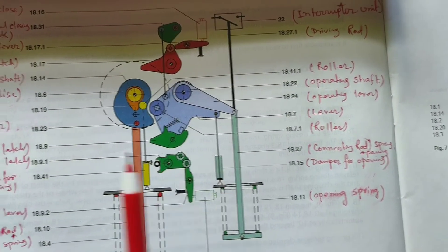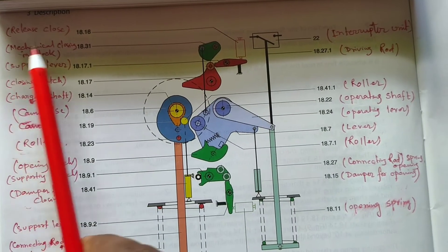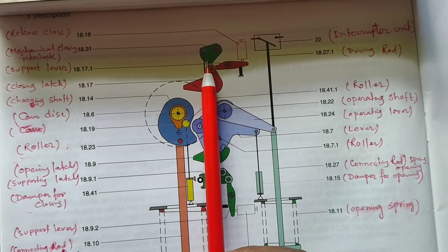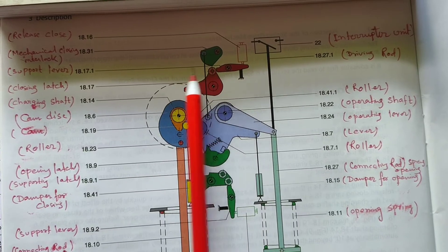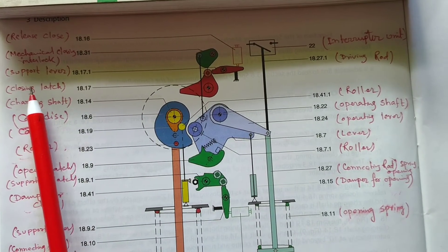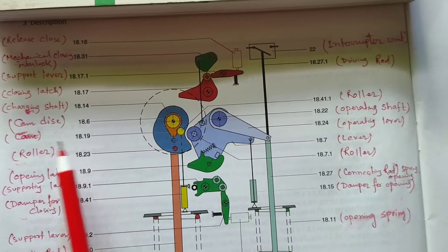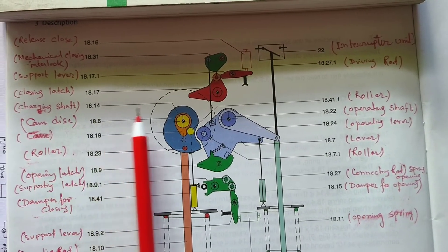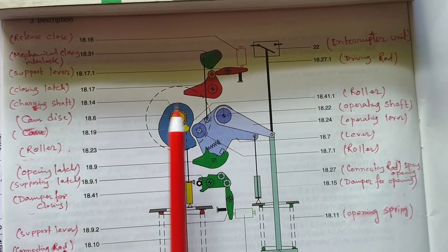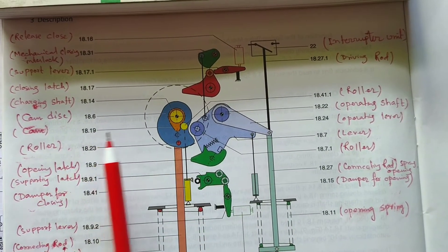Let's discuss about the closing part. This is the release close, this is the mechanical closing interlock supporting lever. This is the closing latch. This is the charging shaft. This is the cam disc — it is called the cam disc.